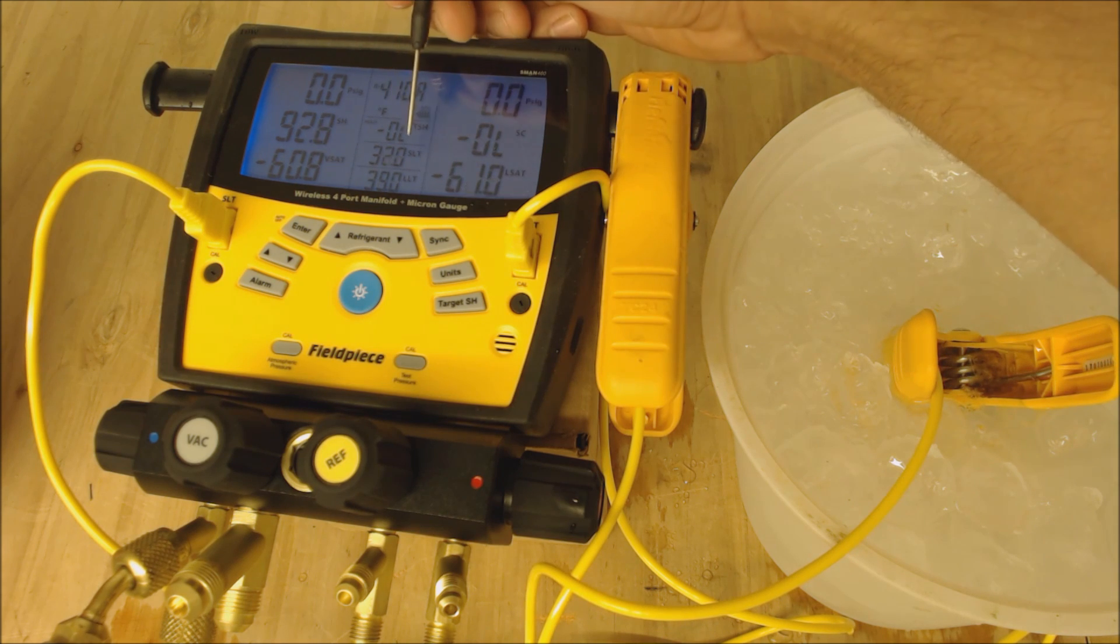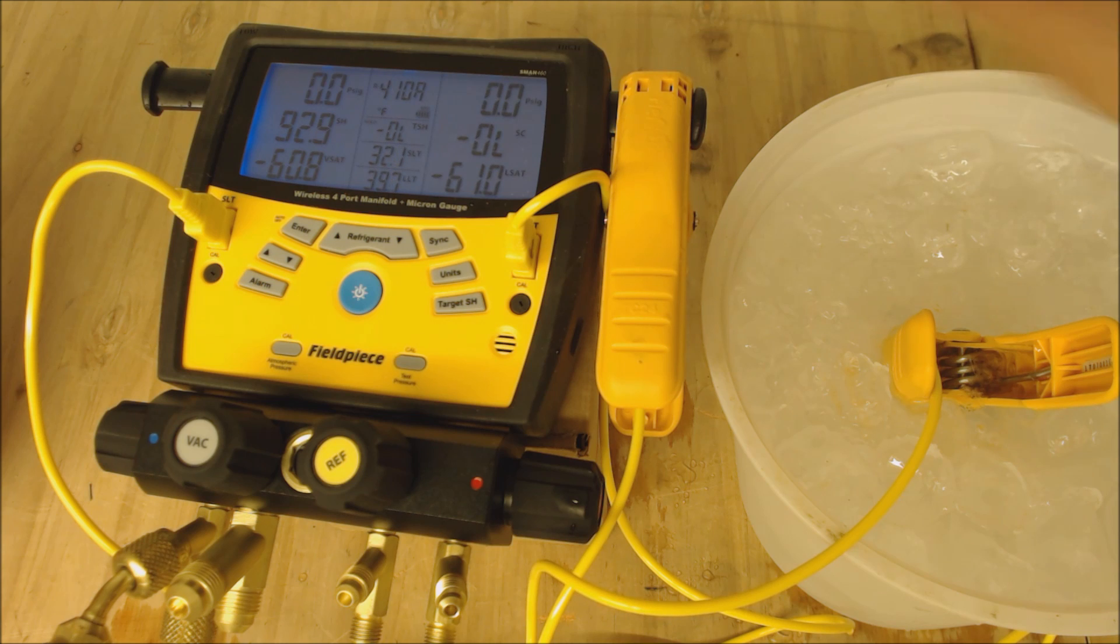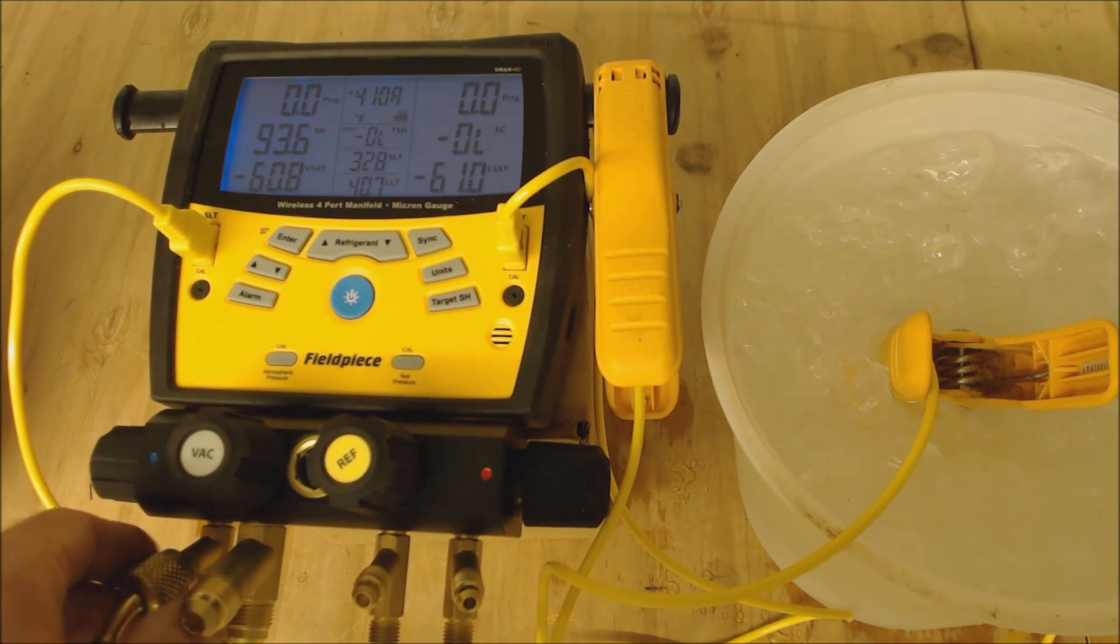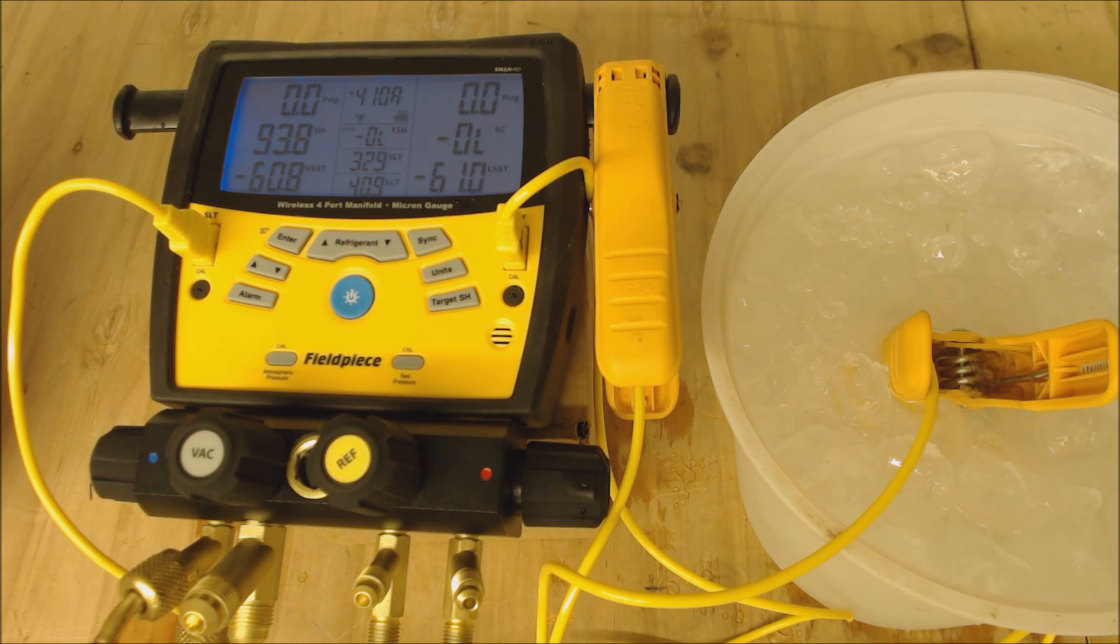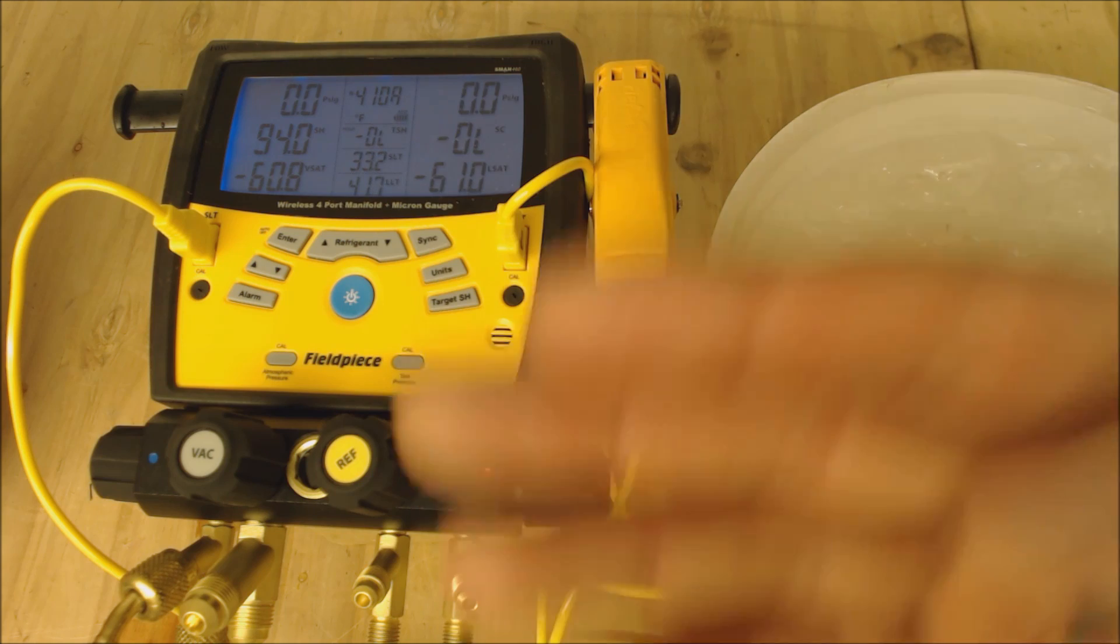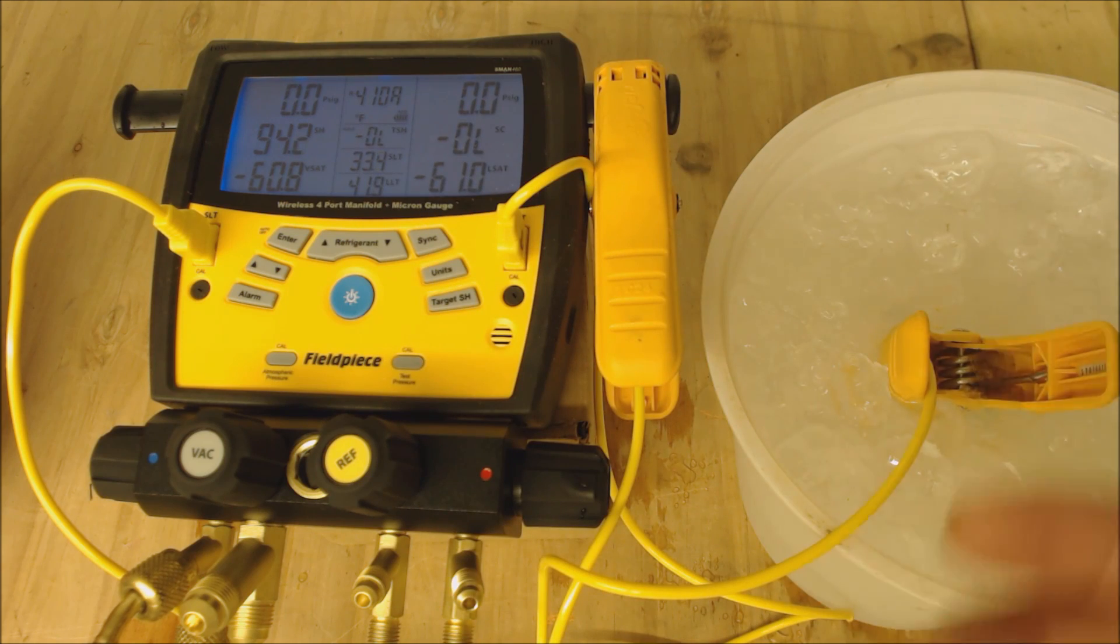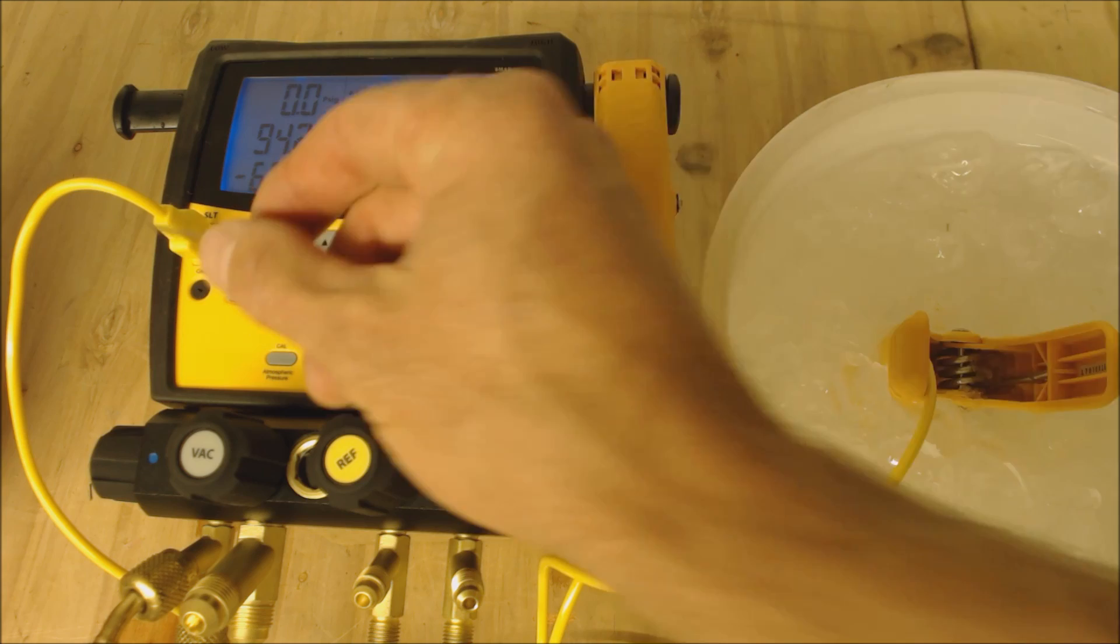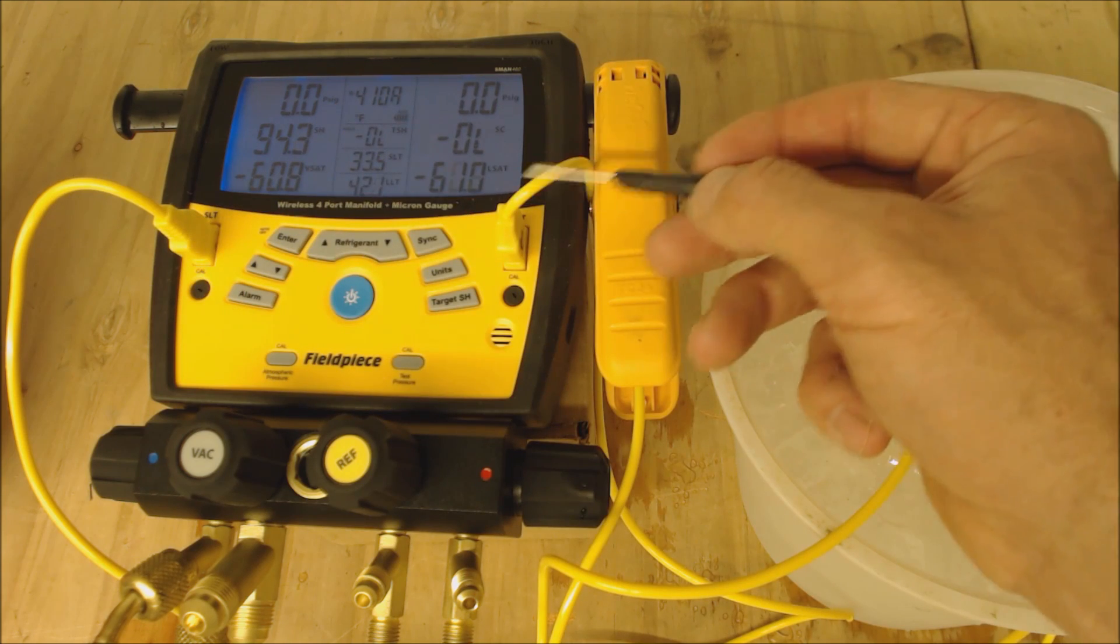Now we're looking at our suction line temperature. We are right there and fairly close, but we're going to give it some time to absorb the temperature. Whether you get this out of the box new or it's just been a while, you want to make sure you recalibrate the temperature clamps because if it got tugged or something, the resistance value might have changed.